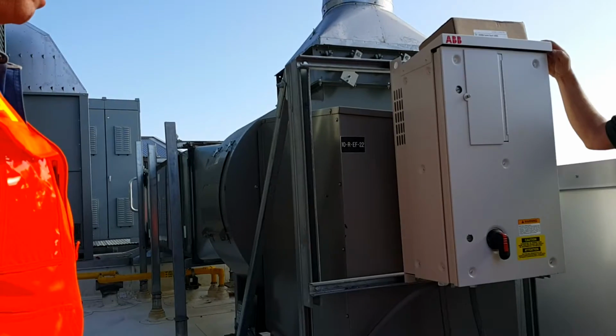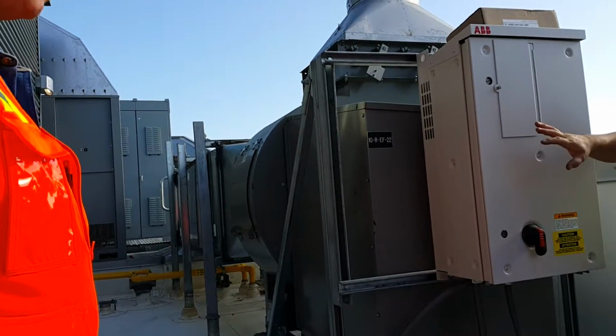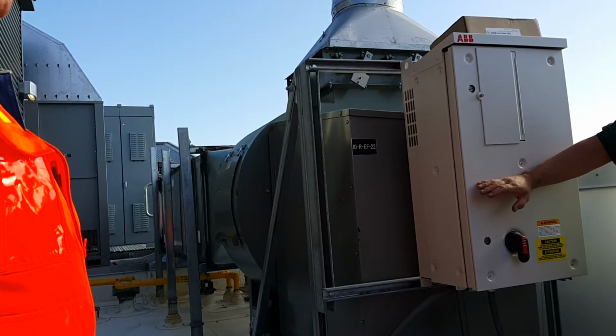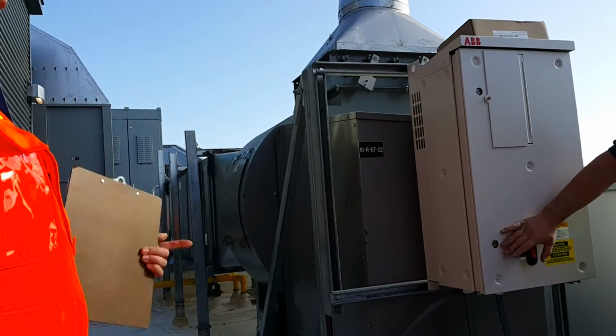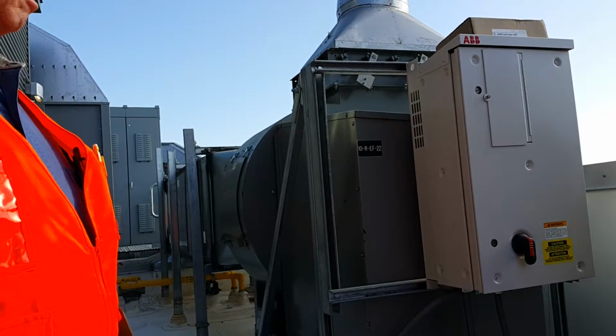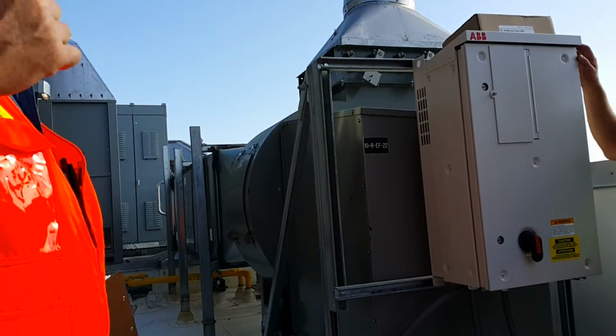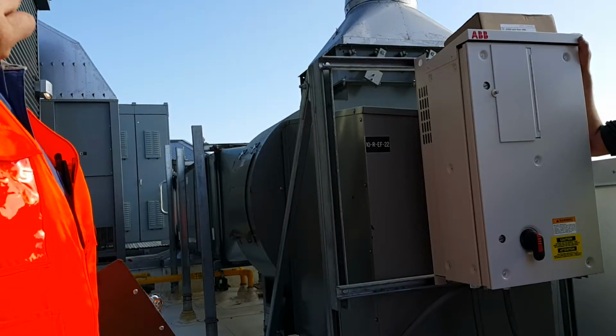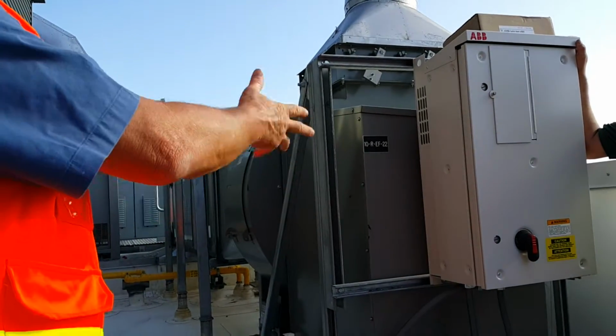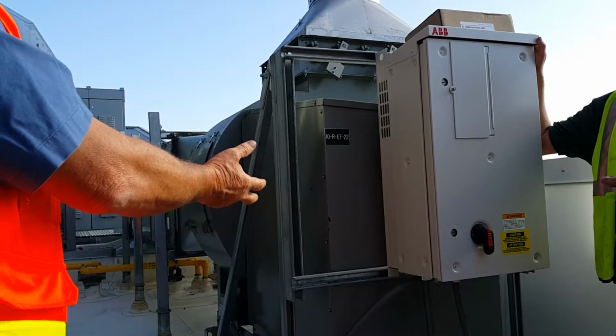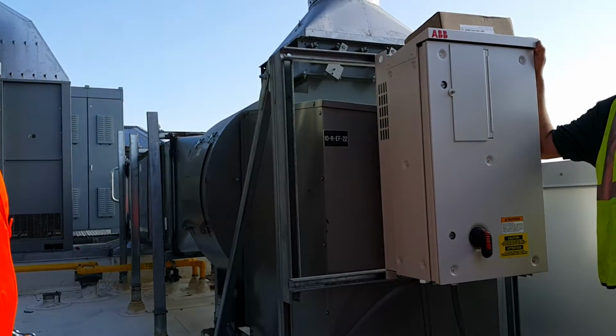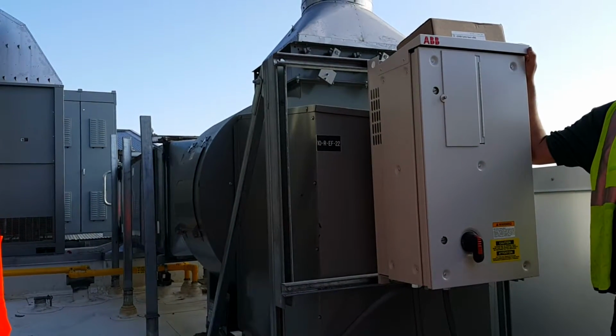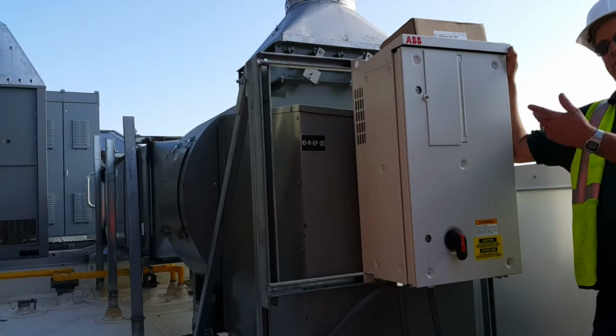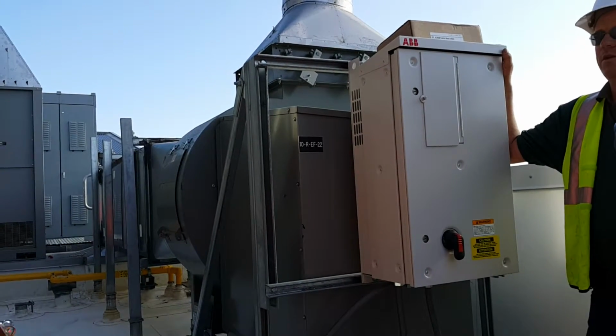Right. So opening that disconnect, we'll still have power here, but if we kill the breaker, then we're dead here. So if we hit the breaker, we don't have to worry about anything, because the drive's going to see no power. It's going to go into an under voltage fault and then go completely off. When you bring it back on, it'll just come right back on and do its normal startup.